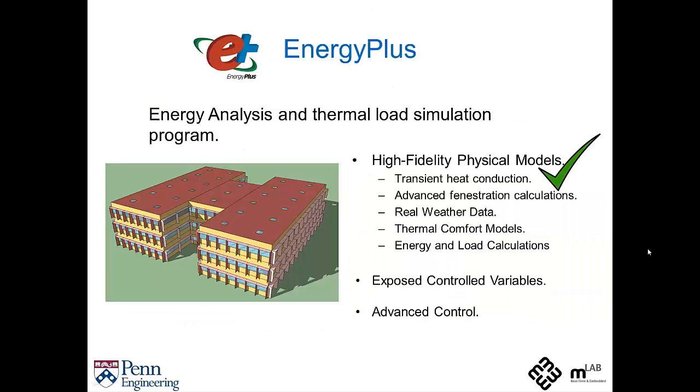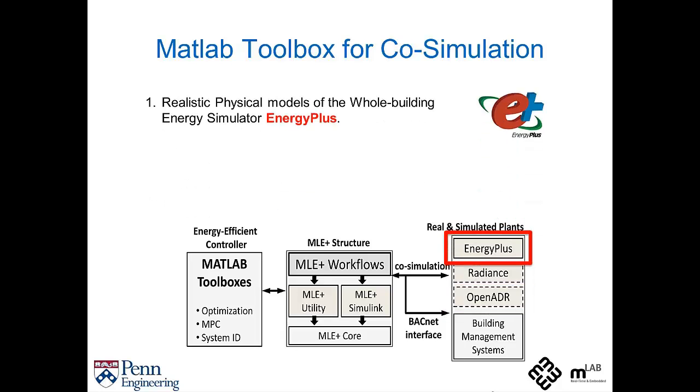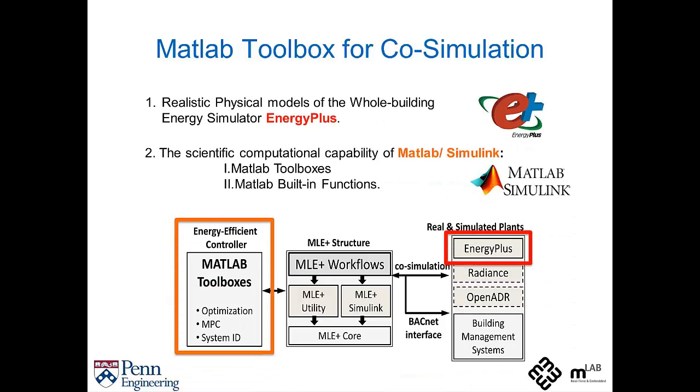However, EnergyPlus does not allow access to certain control variables in its models, making it difficult to implement low-level controls, like setting the damper positions. It also does not provide an adequate control interface, making it very difficult or impossible to implement advanced control algorithms like model predictive control. This is why we want to leverage the high-fidelity physical models of EnergyPlus and the scientific computational capability of MATLAB and Simulink. Towards this goal, we created a co-simulation toolbox, MLE+.